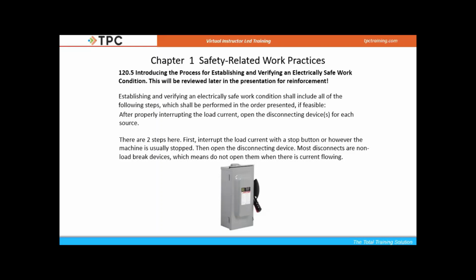Why do we have to do that? Because this disconnect is a non-load break device, which means by its UL listing it is not made to be opened or closed when there is current flowing through it, or when it's under a load. So we make sure first we interrupt the current, then we open this disconnecting means.